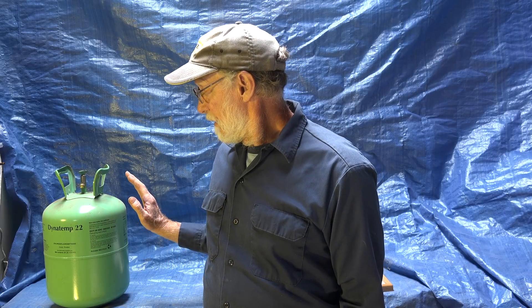R-22 had very good pumping efficiency. Its pressures, if you're comparing it to R-12, are higher — at 70 degrees the saturated pressure would be about 120 psi. So it was a higher-pressure refrigerant than R-12. R-12 was used in air conditioning, but not as much as R-22; R-22 was pretty much the go-to refrigerant for that application.